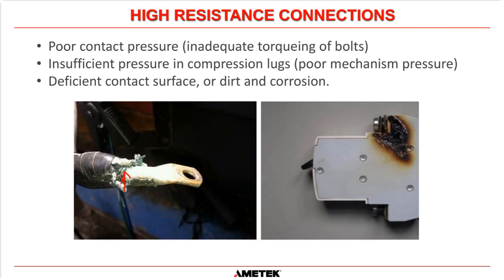And what do high resistance connections do? Well, what this picture shows you on the right hand side. This is a DIN rail mounted switch, and it had either a high resistance connection at the top here, where the lug should have been here, or it was even corrosion or dirt. I don't know what it actually was, but what it caused is that contact to heat up to the extent that it caused that amount of damage from heat. And as you can see, if there was anything else close to that piece of equipment, that also could have got hot, caught on fire, and it could have caused the whole system to go on fire. So I don't know what the outcome of this was, but it's obviously definitely not a good situation, and I'm sure it caused some kind of outage on that piece of equipment.